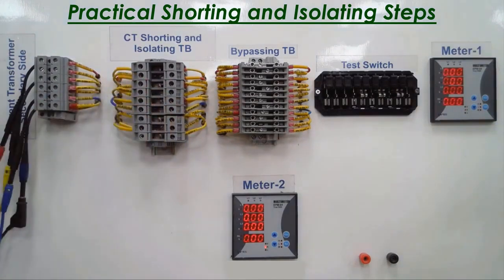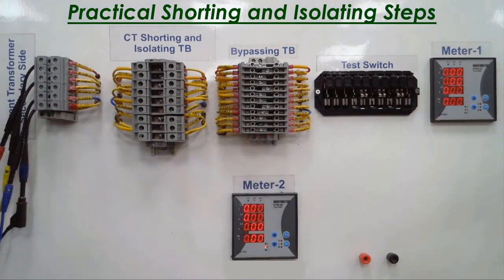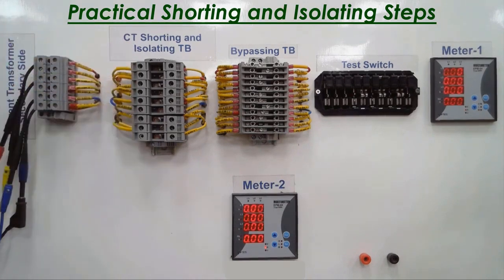In this way, we saw that I did a shorting on the CT circuit and isolated the power meters from the secondary circuit of the CT saturated. I have the Freja 300 or the CMC 156, both of which are considered the CT secondary circuit. This means that if I had made any wrong step here, something like the Freja would indicate high impedance on its circuit, or even the CMC would give you a warning that you have high impedance.